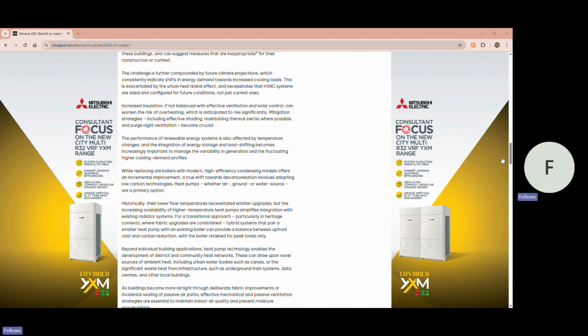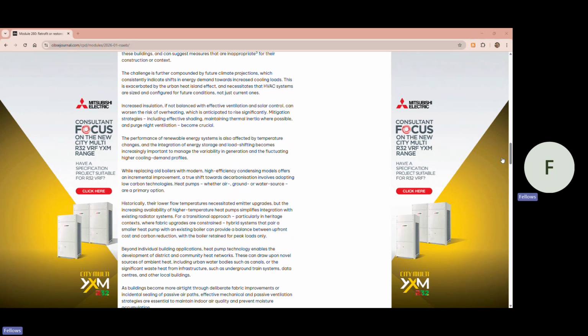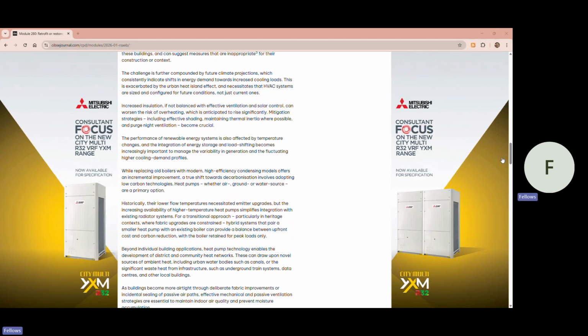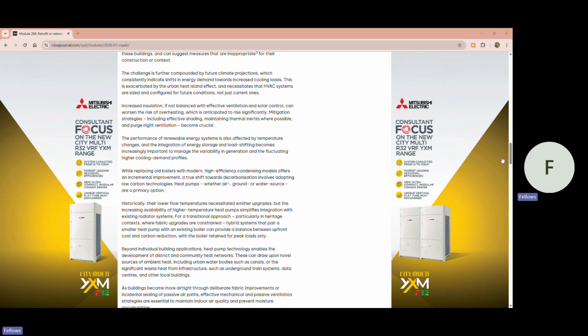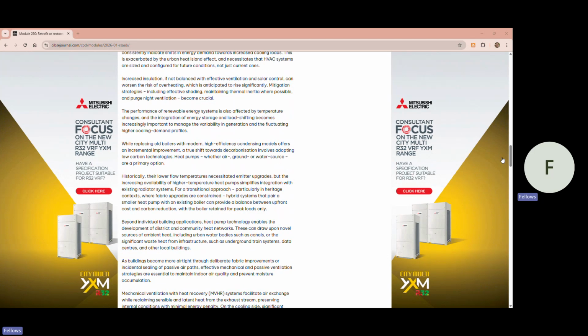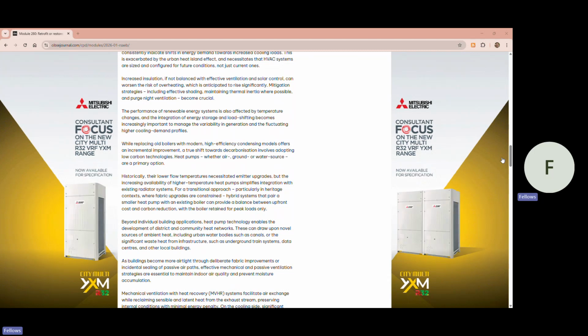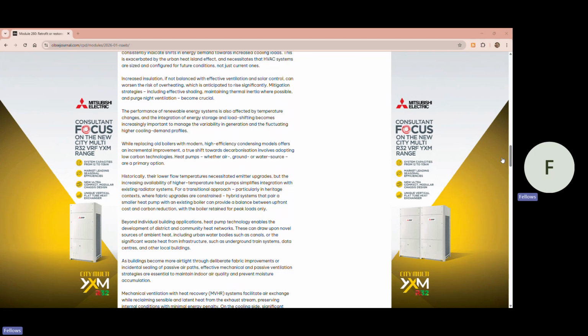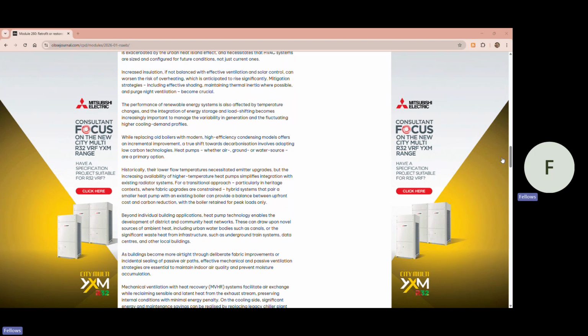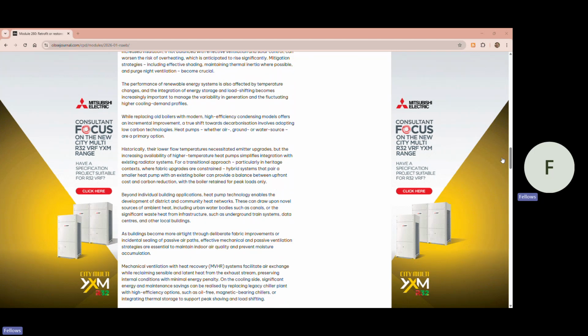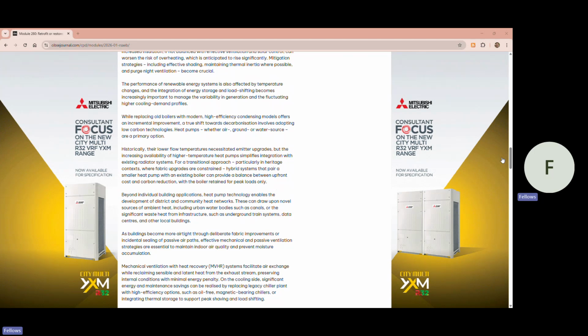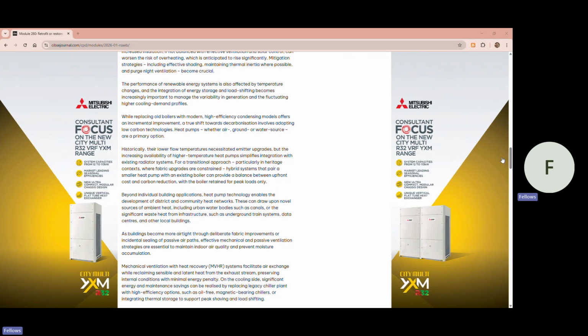The performance of renewable energy systems is also affected by temperature changes, and the integration of energy storage and load shifting becomes increasingly important to manage the variability in generation and fluctuating higher cooling demand profiles. While replacing old boilers with modern high-efficiency condensing models offers an incremental improvement, a true shift towards decarbonisation involves adopting low-carbon technologies. Heat pumps, whether air, ground or water source, are a primary option.